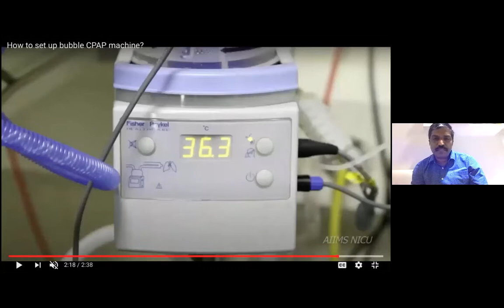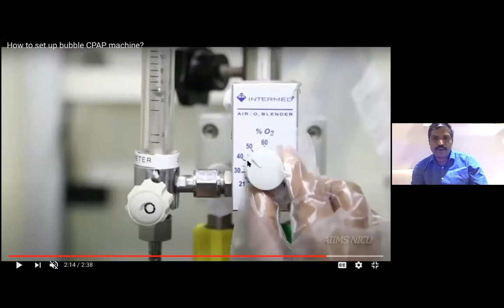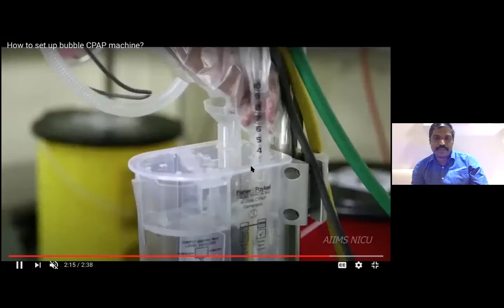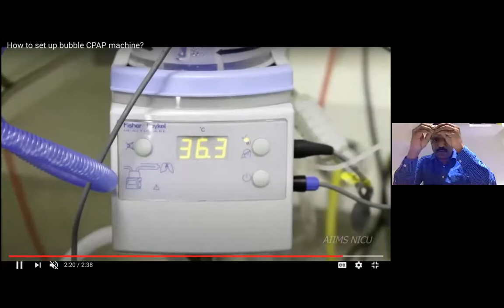So temperature should be 37. Pressure should be 5, FiO2 30%, flow of 5 liters. Look for bubbles. Now we have closed the inspiratory and expiratory limb together. And this temperature should come to 37 before you connect to the patient. So that is how you have now set the machine. Now let us look at how to set the prongs.